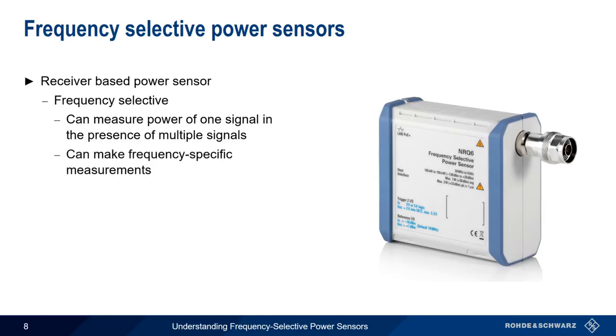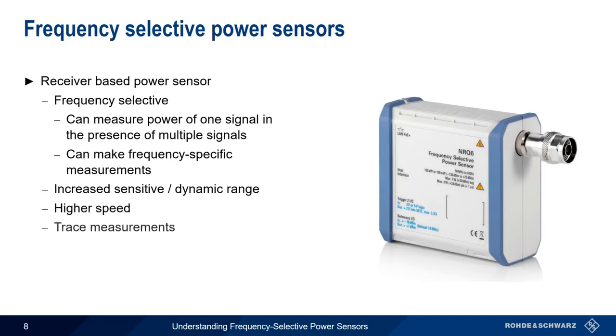In addition, these power sensors offer improvements in both sensitivity and dynamic range, as well as much higher measurement speed. And like a wideband power sensor, a receiver-based power sensor can also support power versus time, or trace measurements. Let's look at some of these features in a bit more detail.